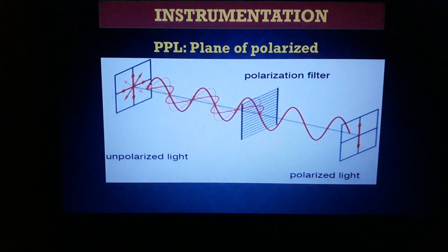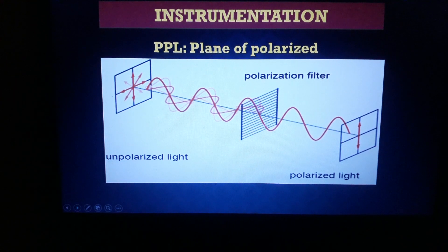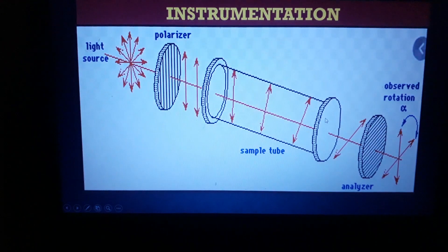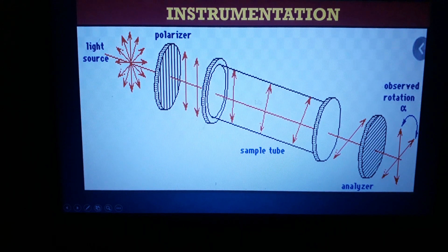Plane of polarized light: a light source produces multi-directional electromagnetic waves. When this multi-directional light is passed through a Nicol prism or polarization filter, it produces a unidirectional, single-plane monochromatic light — this is called polarized light. In the instrument, the light source produces multi-directional light, the polarizer (Nicol prism) converts it to a single plane of light, and this is then passed through the sample tube.